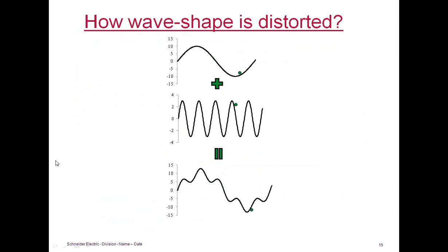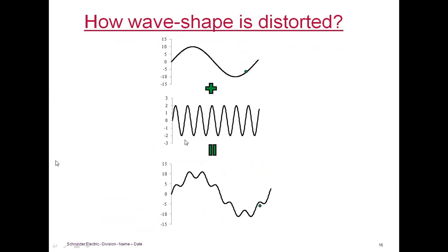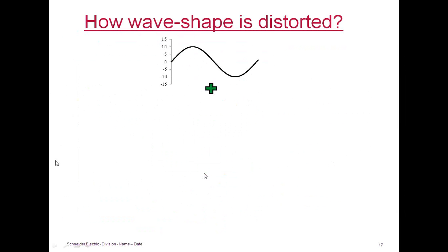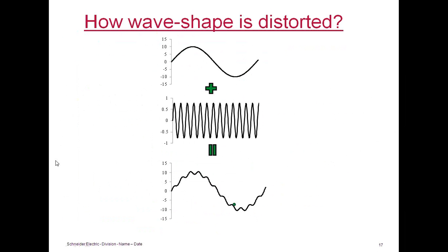The question is how exactly a pure AC will become something else, how exactly the waveform will be distorted. The top one, the fundamental frequency, will add up to the harmonic frequency. In this example, I have the fifth harmonic going just below the fundamental frequency. These two waveforms will add up instantaneously, and you'll get a waveform which is a non-sine wave. This is an example of the fifth harmonic frequency. If you have the seventh harmonic, this is what it looks like, something more distorted. If you have the 11th harmonic, this is what it looks like. This is the waveform of classic 12-pulse converters where the 11th harmonic is dominant.